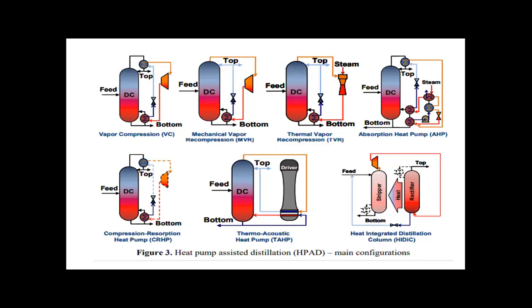AHP uses five heat exchangers, giving it a very high installation cost and therefore a long payback period. If the industry can afford the initial investment and requires refrigeration, then AHP is suitable; otherwise other technologies should be considered. The next is CRHP — Compression Resorption Heat Pump — also called a hybrid heat pump because it uses both compression and resorption. It is a recent approach to take advantage of thermochemical sorption forces.